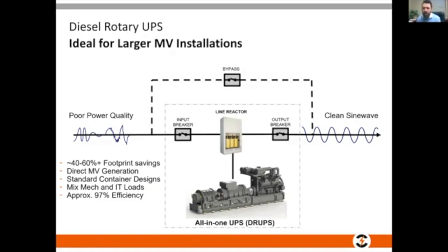I have added a line reactor, which really only allows me to tap into the system, much like an ATS. An ATS allows the diesel generator to supply load by switching across the primary and the secondary. The reactor is a little different—it's just sitting there inline. We call it a choke because of its ability to suppress harmonics and other voltage variations. So as poor power quality comes in, it flows across the inductor, and by virtue of being an inductor, it suppresses large fluctuations, giving us a nice clean wave. I'm also tapping into that inductor, and my machine ensures we have a really nice clean sine wave.